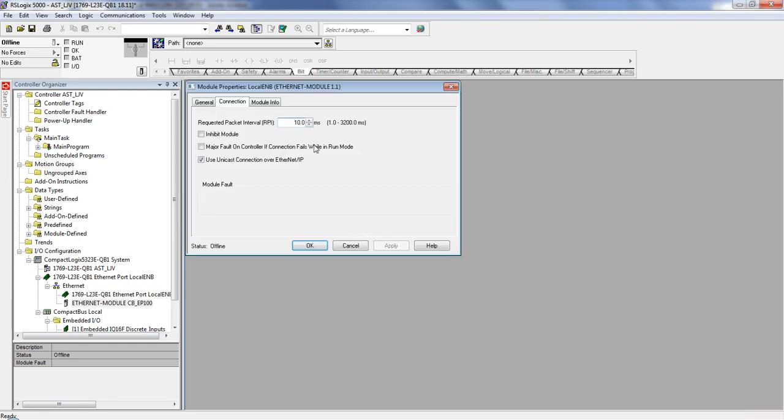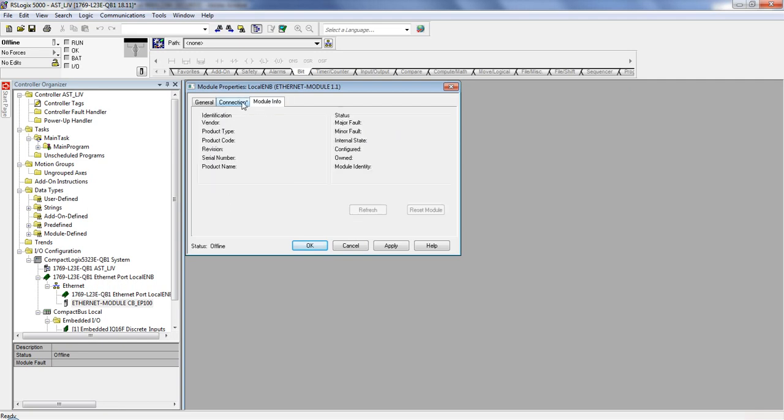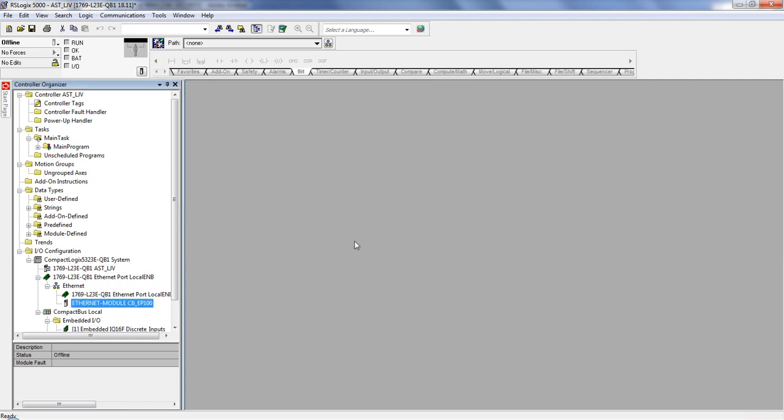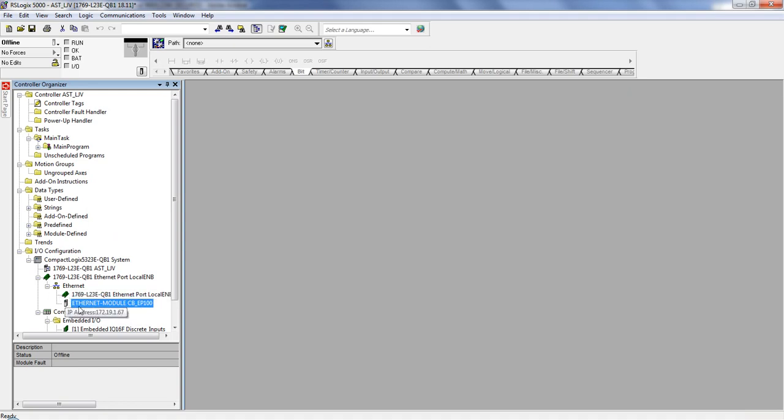So click OK. The request packet interval. This is going to be how fast we're going to refresh our data. So let's say I want to do 5 milliseconds. So this data is going to bounce back and forth and refresh every 5 milliseconds. Click Apply, click OK. All right. So once we've done that, I see my Ethernet module right down here. You get the icon after you install the EDS file.